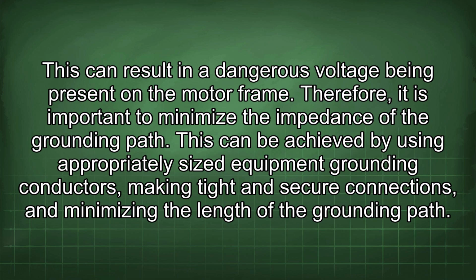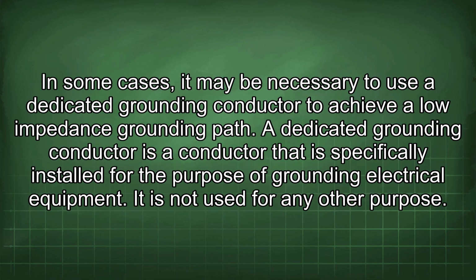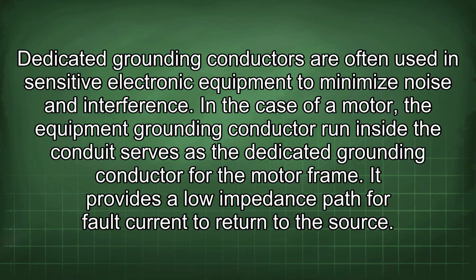This can be achieved by using appropriately sized equipment grounding conductors, making tight and secure connections, and minimizing the length of the grounding path. In some cases, it may be necessary to use a dedicated grounding conductor to achieve a low impedance grounding path. A dedicated grounding conductor is a conductor that is specifically installed for the purpose of grounding electrical equipment. It is not used for any other purpose. Dedicated grounding conductors are often used in sensitive electronic equipment to minimize noise and interference.